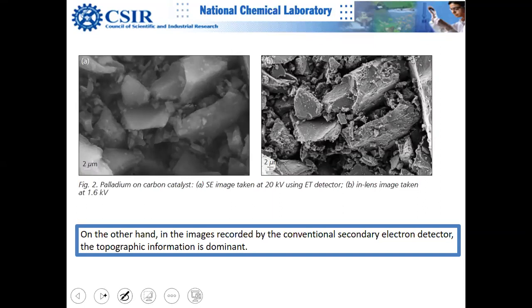An example showing palladium on carbon: the image taken using the Everhart-Thornley detector at 20 kV compared to the in-lens image at only 1.6 kV shows that the in-lens image is much better quality, even though only one-tenth of the accelerating voltage is used.